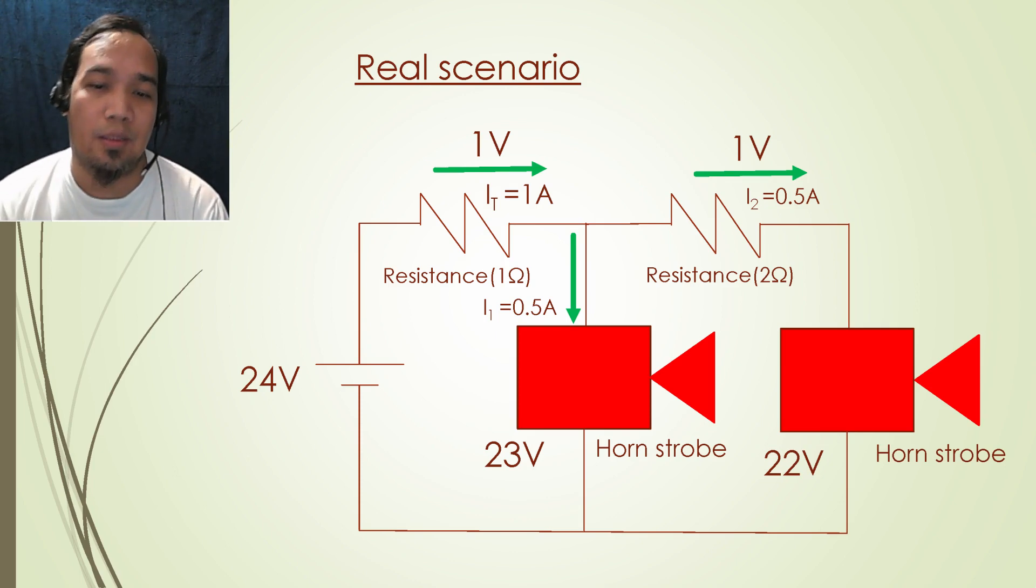You will notice that the voltage received from the first device is reduced to 23 volts due to the voltage drop from the first cable run, and then reduced again from 23 volts to 22 volts received from another device because of the second cable run.